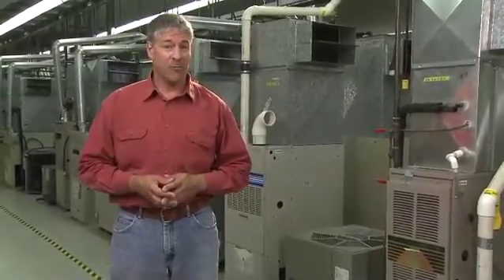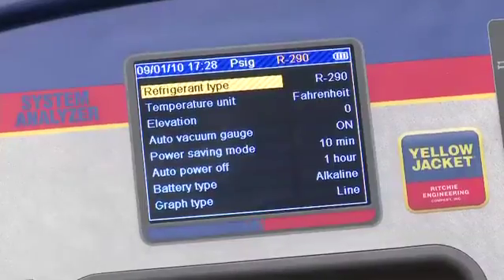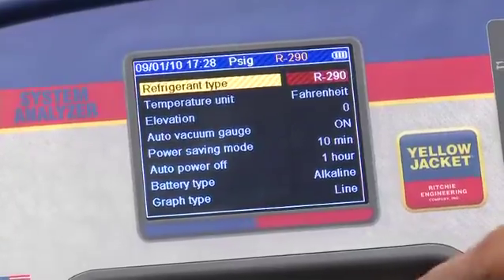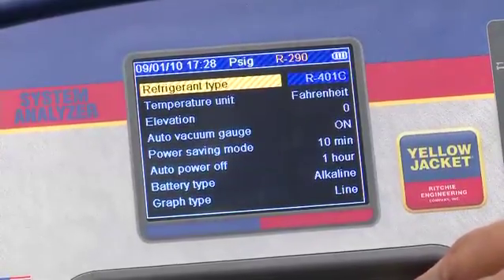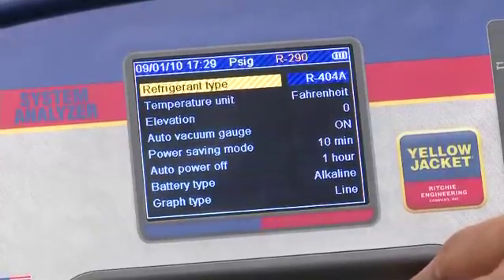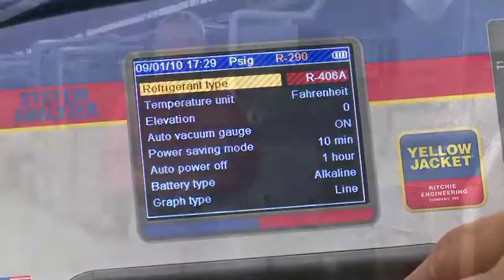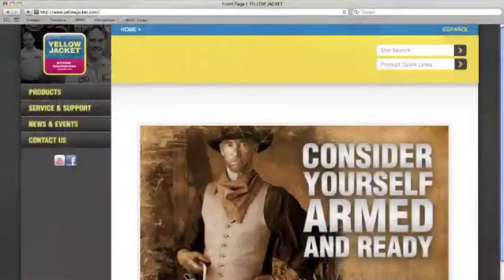There are two ways you can set refrigerant type and temperature unit. The first is through setup from the main menu. Refrigerant type is the first option on the screen, and when you press enter you can scroll through close to 100 pre-loaded refrigerants using the up and down keys. Flammable refrigerants are highlighted in red. When you find the refrigerant you want, press enter to set. The list of refrigerants is updated periodically, so check yellowjacket.com to make sure you have the most current list.